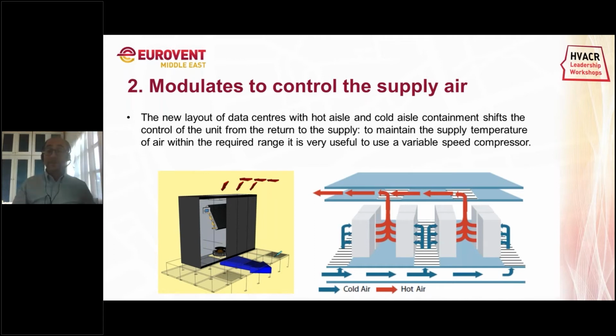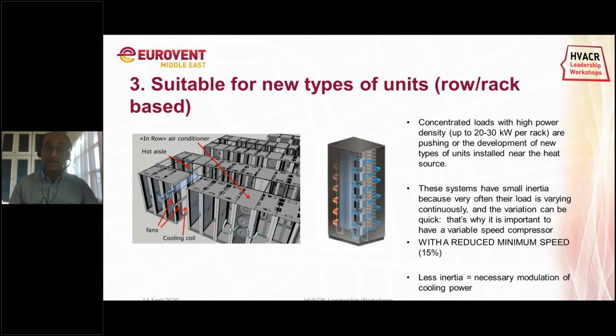Third reason, this control of temperature is combined also to a reduced inertia of newer systems. So with newer types of units, like in-rack units or even totally contained units like this one, somehow I'm clicking somewhere, sorry. With the units with a reduced air volume, so not large room conditioning, but rack-based air conditioning, a reduced inertia might require even more capability of modulation, and especially a wide range. These technologies can allow you to have a minimum speed of 15%, so better fitting also a variable load, something that is going to happen more and more.